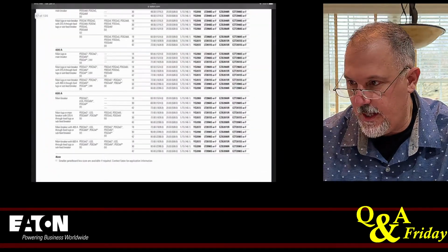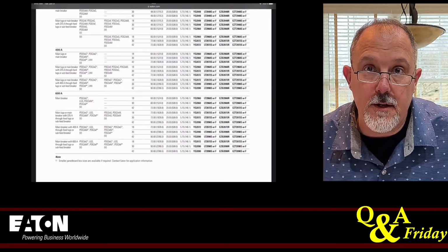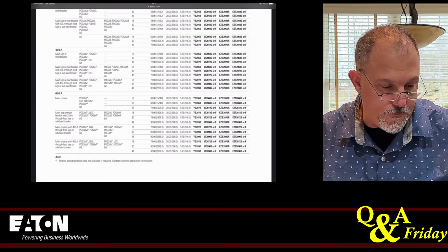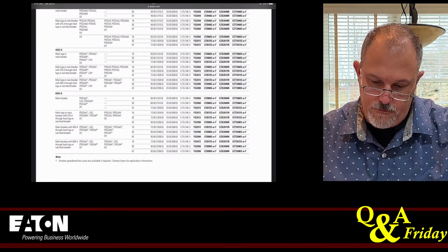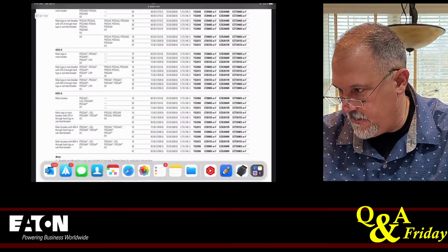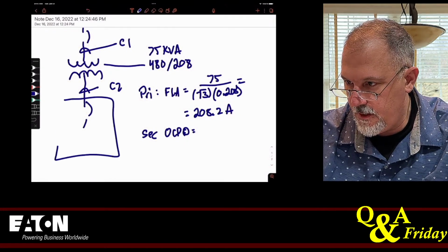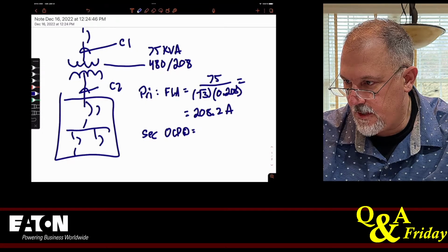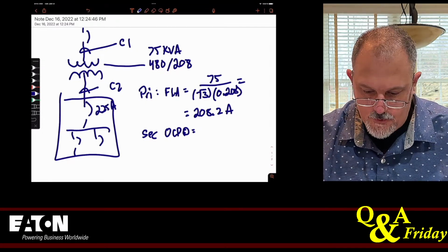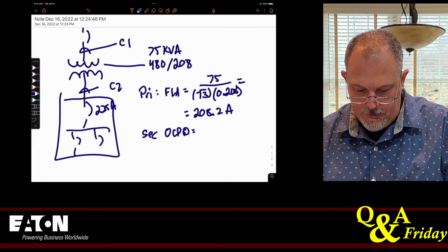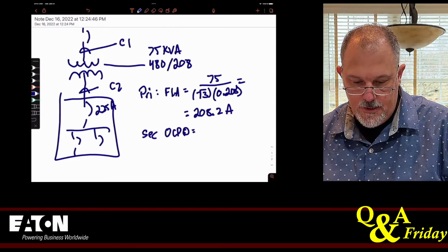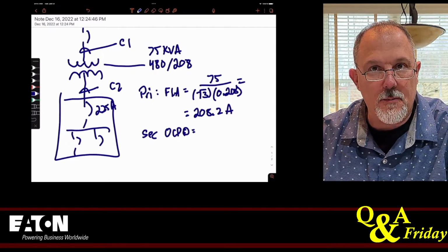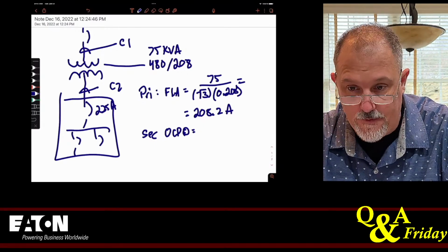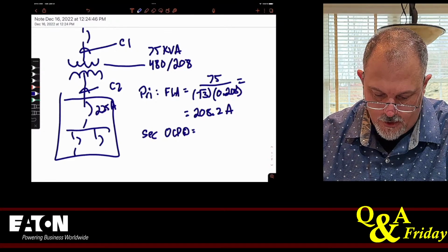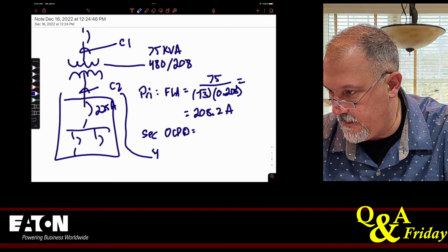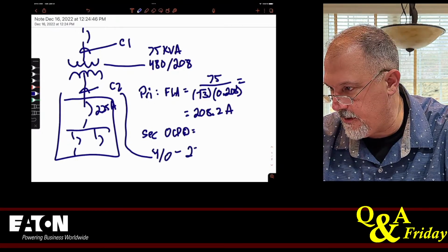225 amp panel board. So what is the conductor that I need? I need at least 225 amps of conductor. So then I go to 310.16, and we'll say this is 225 amps. I need 225 amps worth of conductor. You guys and gals out there probably know this even better than I do: 75 degrees C, because I'm landing on an overcurrent device, going into equipment that's rated 75 degrees C. For 225 amps, I could go with a 4-aught conductor. A 4-aught conductor is 230 amps.